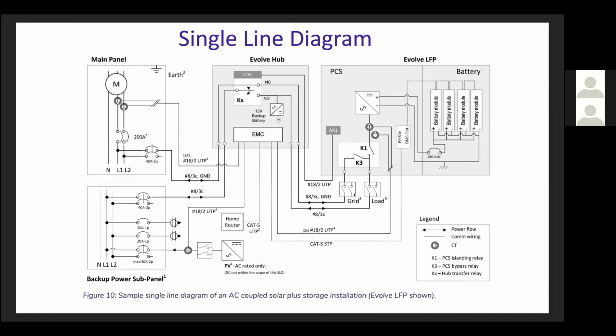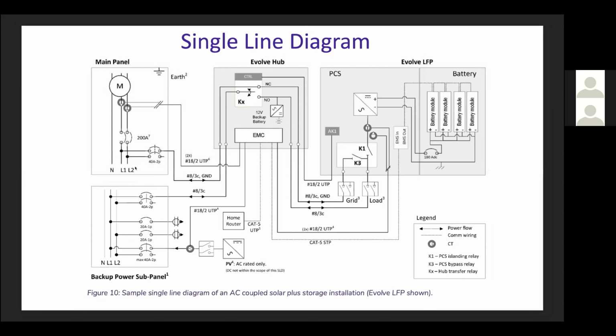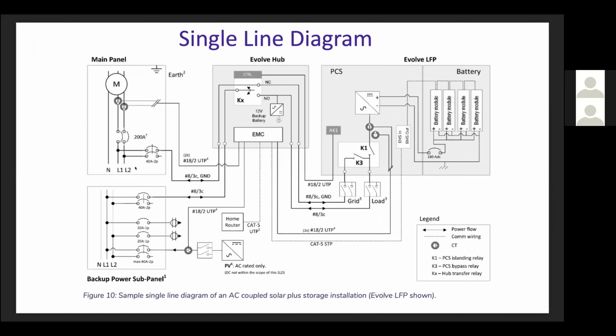And again, these required disconnects are shown here. NEC required disconnects. If your AHJ requires you to have a disconnect at the main panel location, then electrically, whether you put it here in front of the hub between the service panel and the hub, which will cut off your backup loads subpanel, or if you electrically locate it here but just physically locate it by the main service panel, that's going to be in addition to the disconnects that are required at the inverter location. So please remember that. It will save you headaches when it comes time for inspection and for commissioning the system, as well as servicing it whenever necessary.